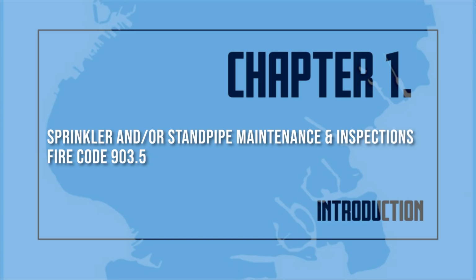3. At least once in 5 years, the fire department connection or connections for a sprinkler system shall be subjected to a hydrostatic pressure test to demonstrate its suitability for fire department use. The test shall be arranged to be conducted by a master fire suppression piping contractor in the presence of a fire department representative. The contractor shall be hired by the owner or the owner's representative. 4. There shall be 1 or more employees with a certificate of fitness to inspect the sprinkler system following the standard of the National Fire Protection Association 25 of 2002.